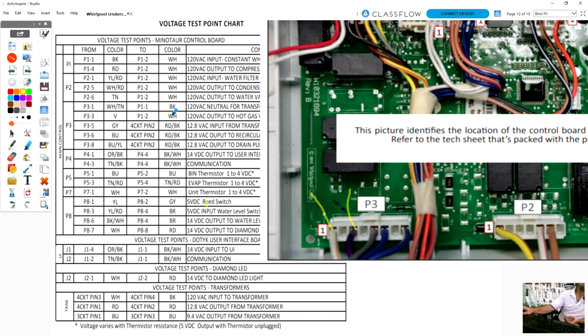And what are you testing there? We're testing these two here, which is a white with a tan, and this is our violet wire here. This is our neutral and our hot gas valve. This is what sends power to harvest the ice, for example. So that's what this chart is telling you, is where you can put your meter on the board to make voltage tests for troubleshooting.